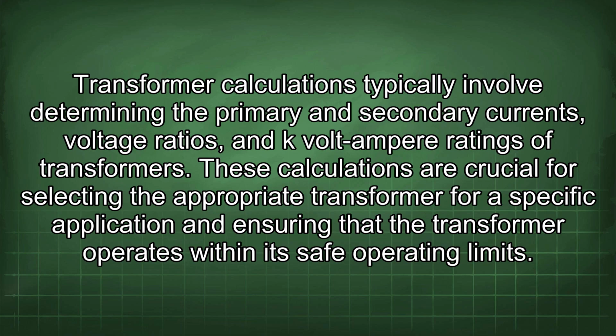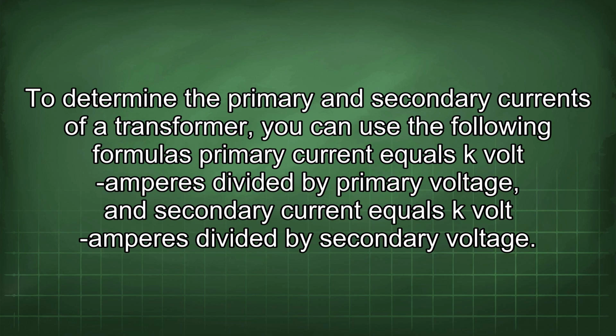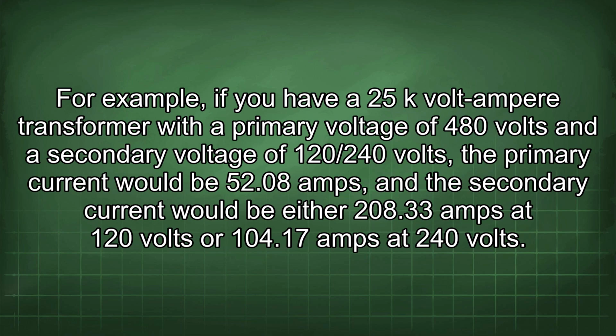Transformer calculations typically involve determining the primary and secondary currents, voltage ratios, and kVA ratings of transformers. These calculations are crucial for selecting the appropriate transformer for a specific application and ensuring that the transformer operates within its safe operating limits. To determine the primary and secondary currents of a transformer, you can use the following formulas: primary current equals kVA divided by primary voltage, and secondary current equals kVA divided by secondary voltage. For example, if you have a 25 kVA transformer with a primary voltage of 480 volts and a secondary voltage of 120/240 volts, the primary current would be 52.08 amps, and the secondary current would be either 208.33 amps at 120 volts or 104.17 amps at 240 volts.